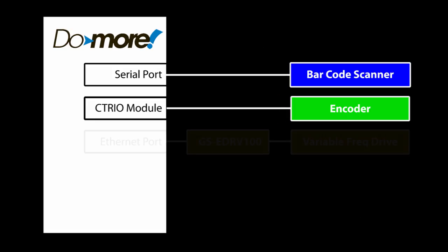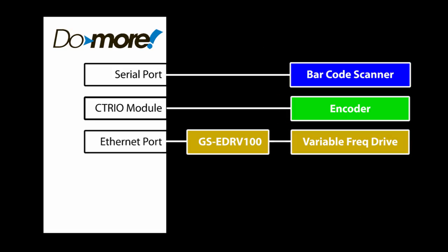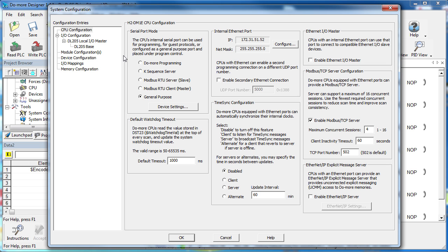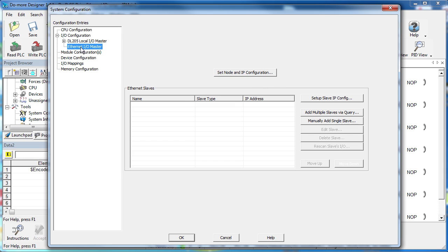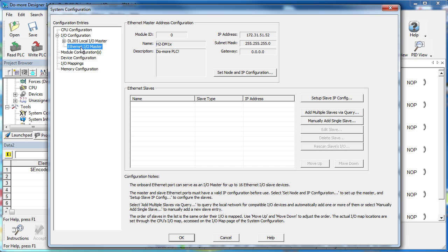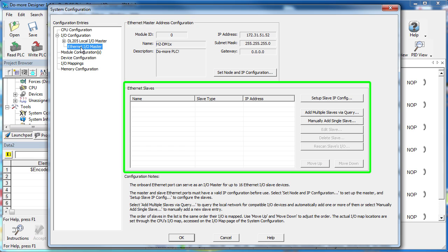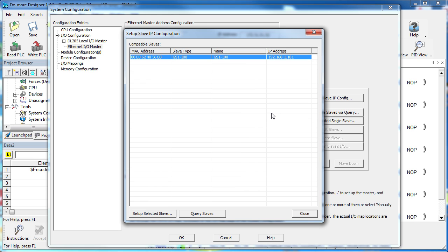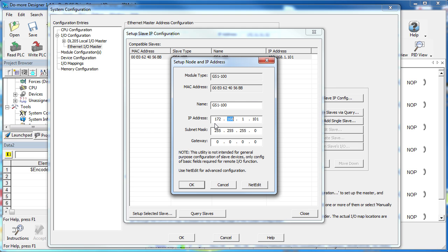Let's set up the variable frequency drive on the Ethernet port. Where do we start? Same place as before – go to hardware configuration and start at the top with CPU and work our way down the configuration list. Enable the Ethernet I/O since that's how we talk to the GS-EDRV100. That creates a new Ethernet I/O entry in our I/O configuration. Click on that to configure the Ethernet I/O network. You can change the Do-more's IP configuration here and modify the slaves down here. Before you add slaves to this Ethernet I/O master list, you need to make sure they are all in the Do-more's domain. How do you do that? Just like everything else – start at the top, work your way down. This first button scans the network and identifies all of the Ethernet I/O compatible devices. Let's get this IP address on the Do-more's network and let's change the device name to Conveyor Motor.